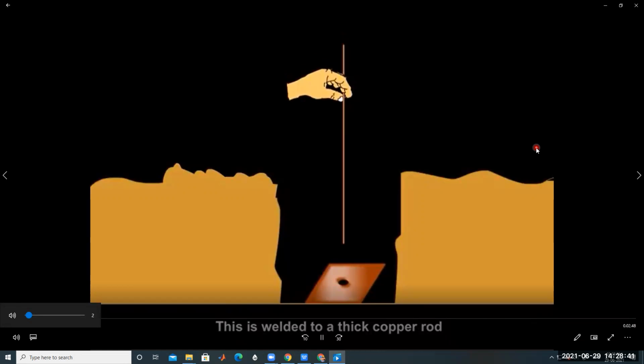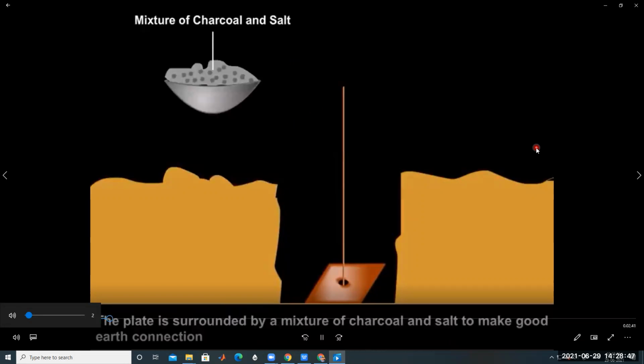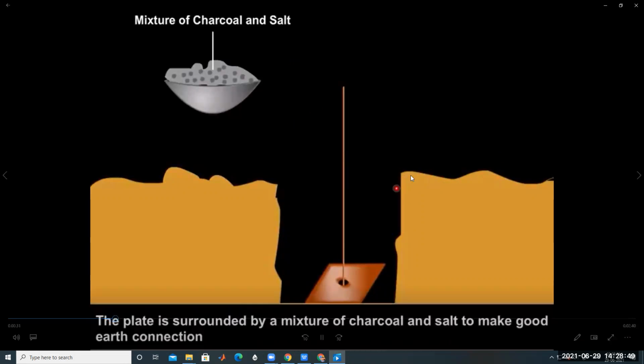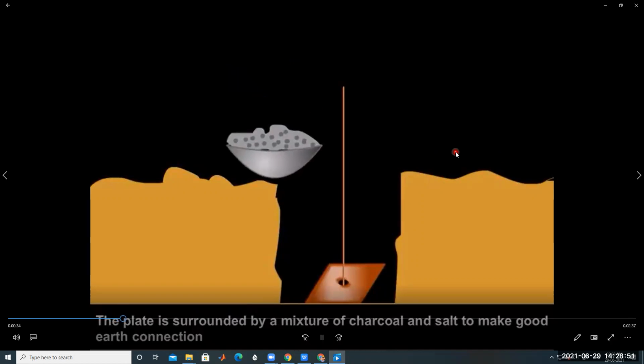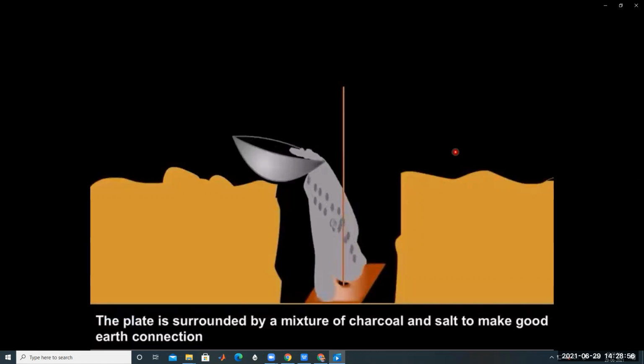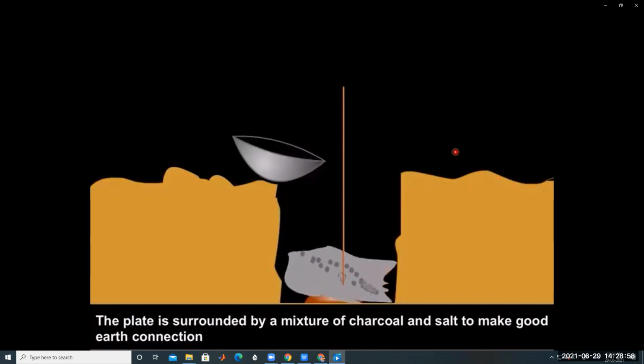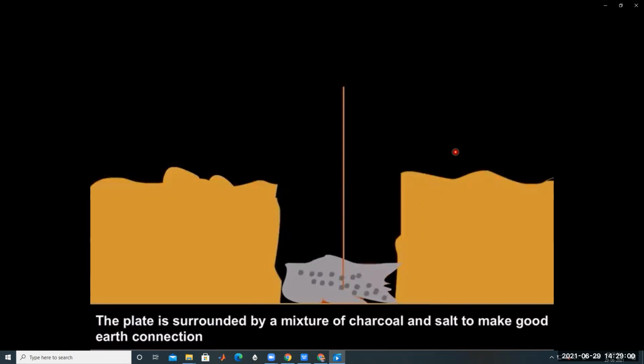This plate is welded to a thick copper rod. So like this, the copper plate or steel plate is welded to the copper rod. And the plate is surrounded by a mixture of charcoal and salt to make a good earth connection.